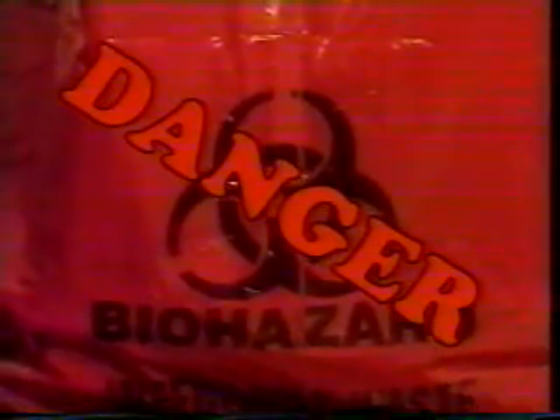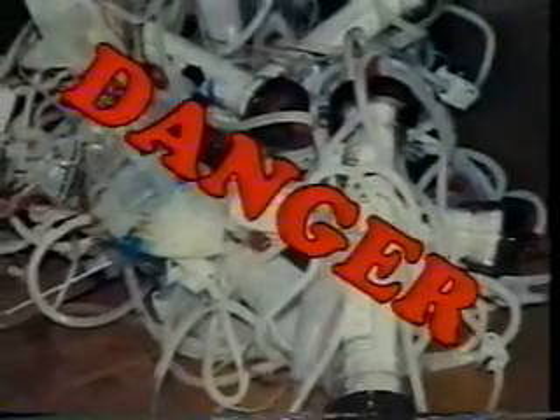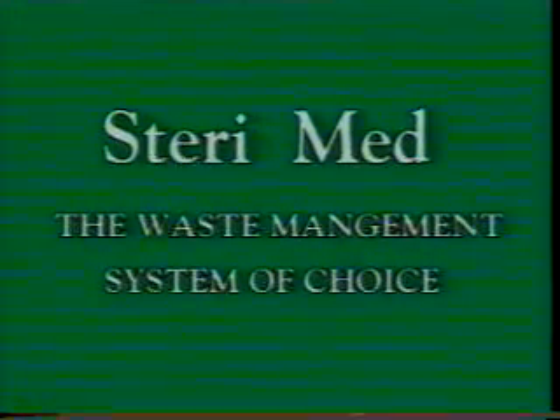In each cycle, a Steri Med unit treats a standard 1.2-meter red bag. One Steri Med unit has the capacity of handling 375 liters of medical waste per hour, or over 200 tons a year. Steri Med — the waste management system of choice.